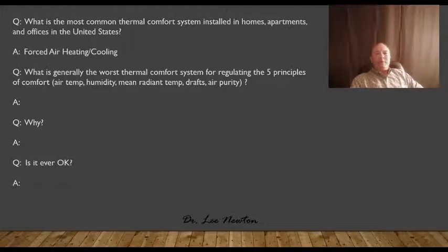If the air in your room is 70 degrees and it's wintertime, and you stand close to a window and you say, wow, I'm cold, and then you look at the thermostat and it's reading 70 degrees and you've set it at 70 degrees, so it's not heating, but you say, wow, I'm cold, you are radiating more heat to the window than is being radiated back at you. There is no equilibrium established there and you're losing heat. That's why you feel cold. That's what mean radiant temperature means, and that's something that when we design structures we have to think about.